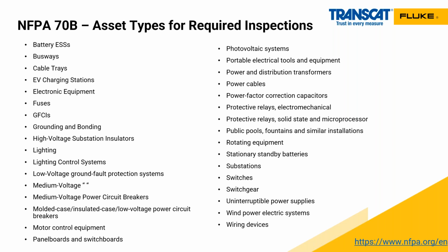And if you think about three-phase systems like a motor, there's actually 6 fault paths on that. Phase A to B, phase B to C, C to A, A to ground, B to ground, C to ground. It only takes one. If it gets to the point of fault, it's literally going to blow up. So I would be looking at the most critical ones if I were you. I don't know what business you're in, but if you have maintenance shutdowns, or we're walking around with a thermal imager and we see these overheated devices, you're going to want to shut it down as soon as you possibly can and test the insulation to see how much life or health we have left in that insulation.